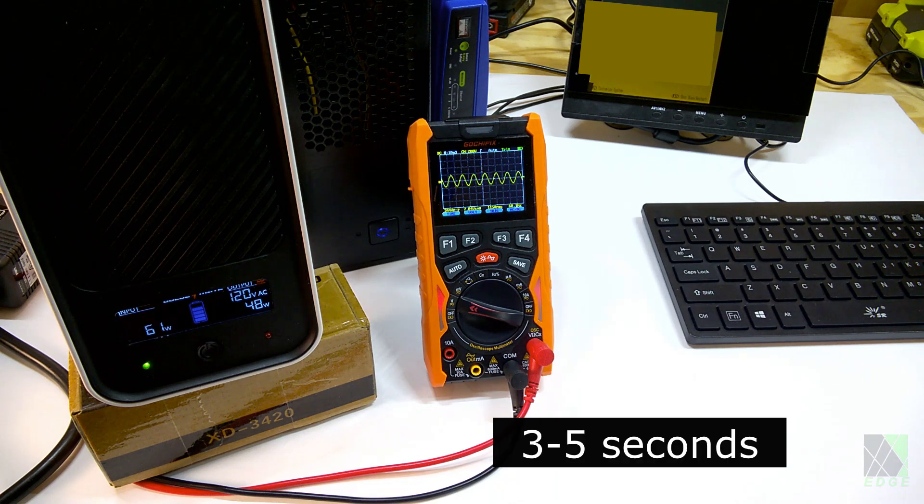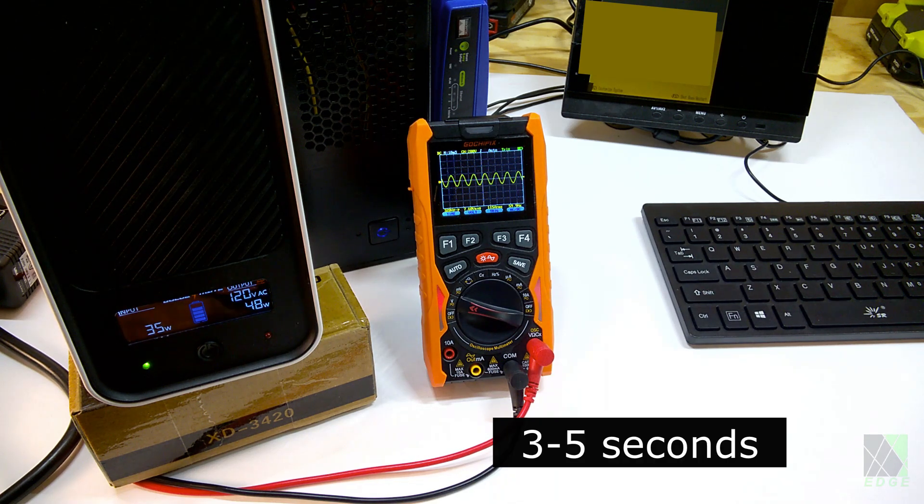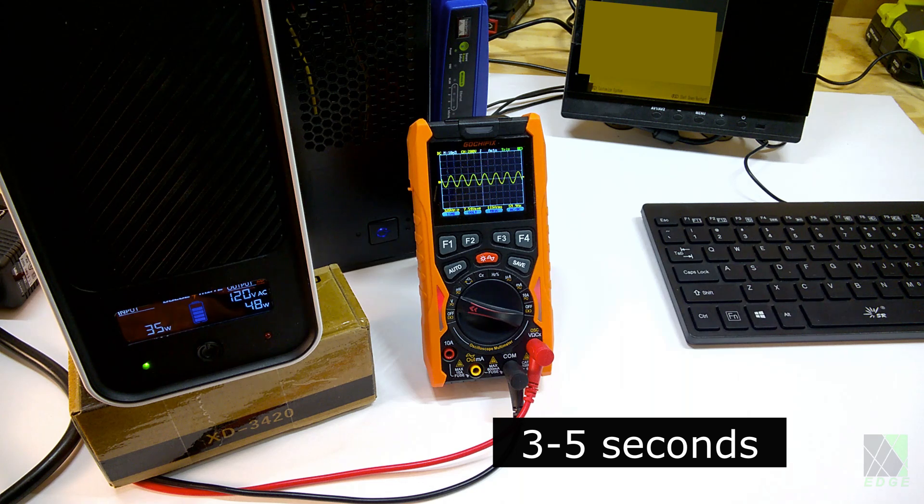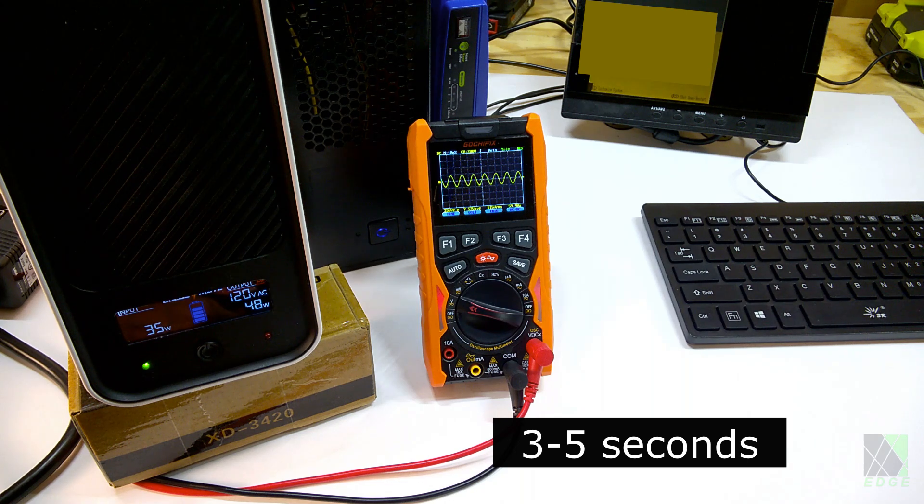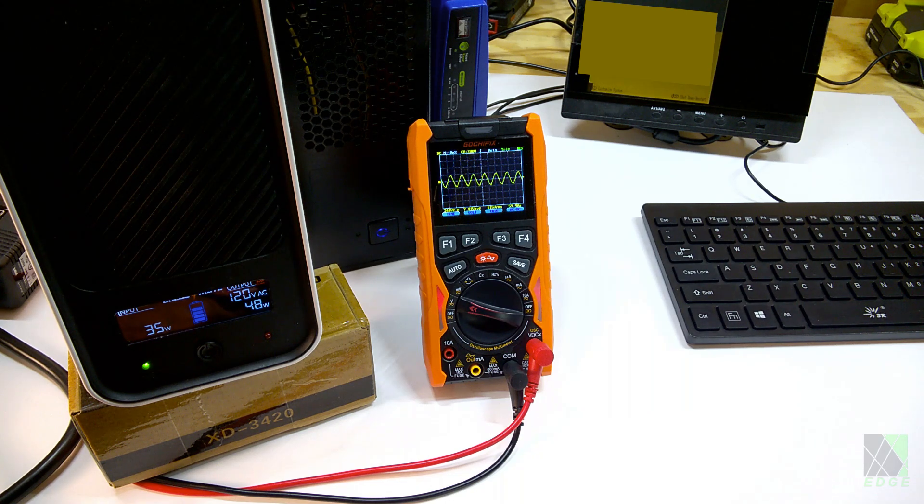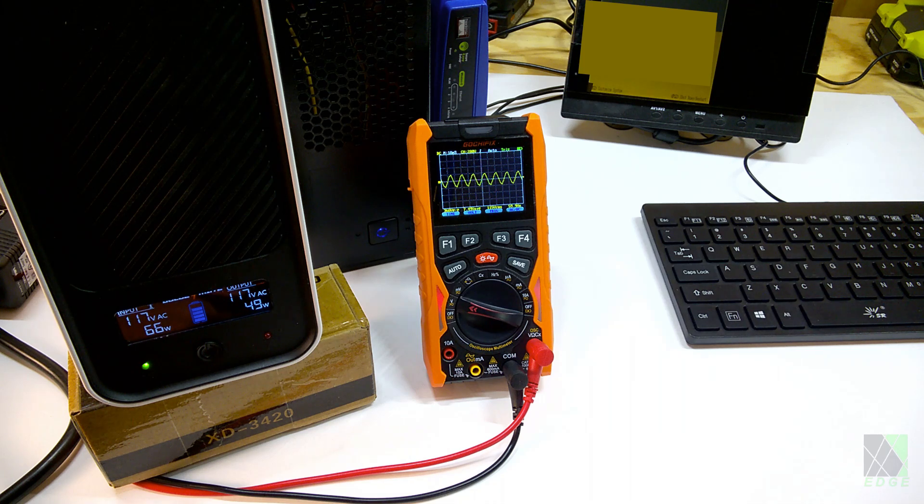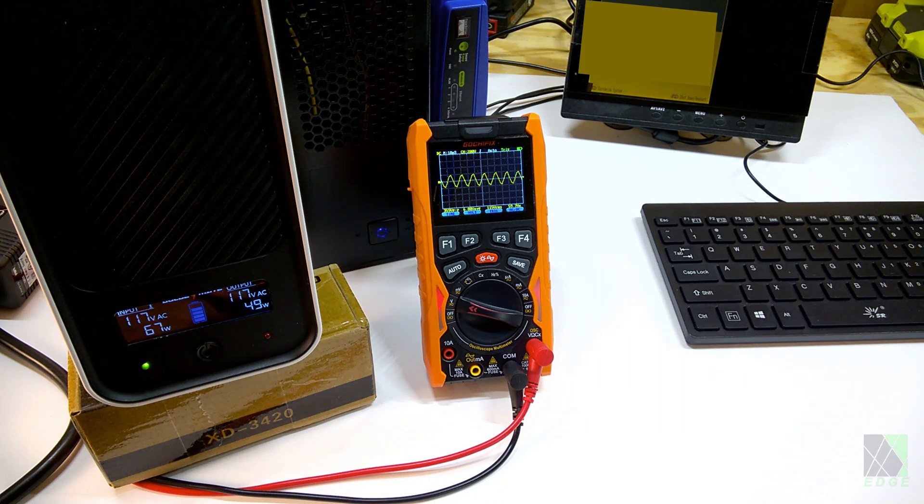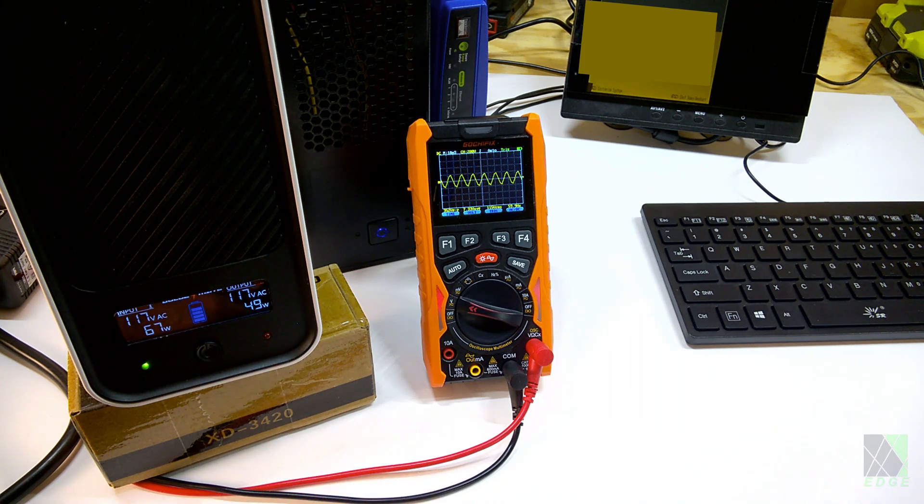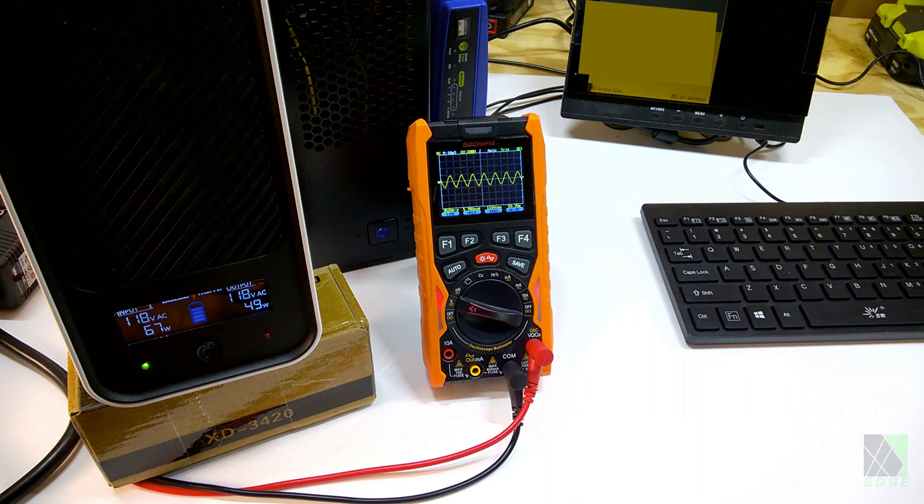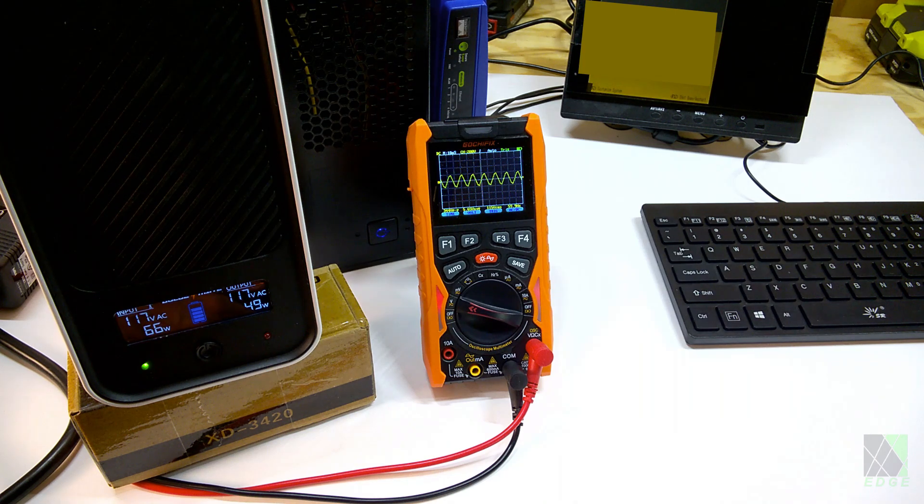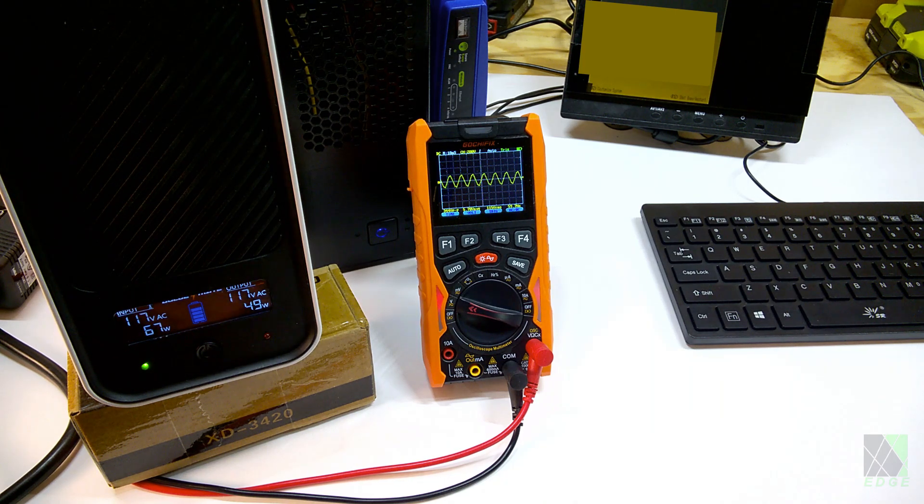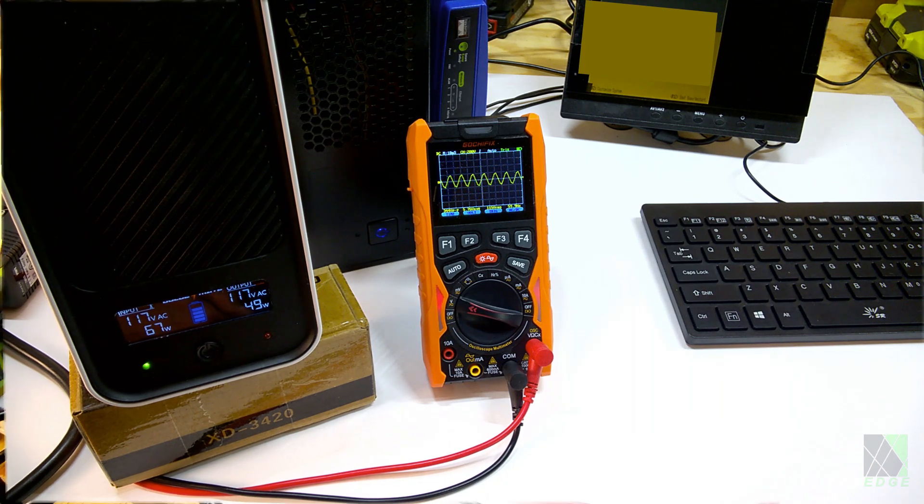It's in. I'm going to say something like five seconds. So five seconds of hysteresis means that this UPS is smart enough. If the power comes on and then goes back off again, it will hopefully avoid that, and hopefully avoid crashing your equipment.